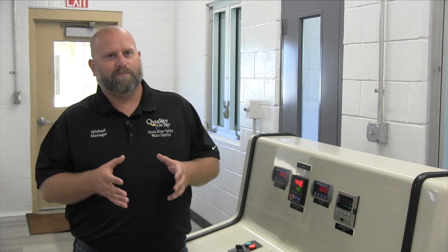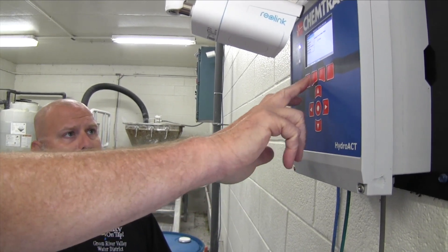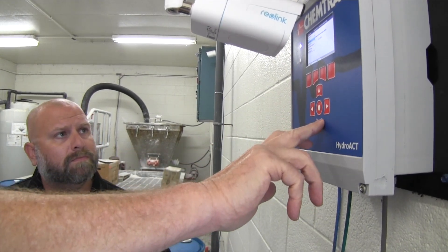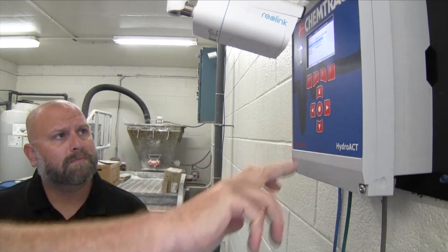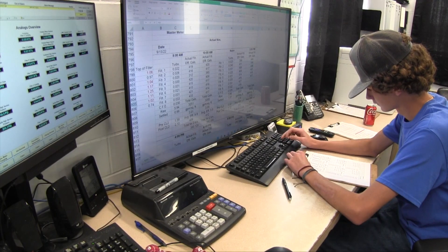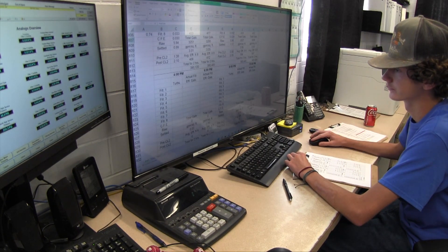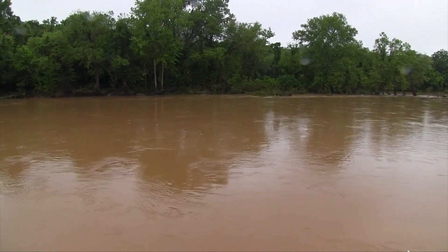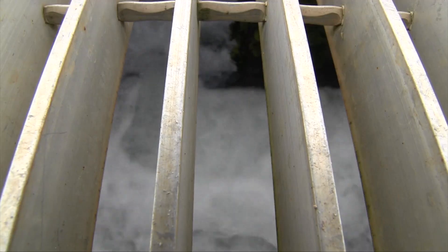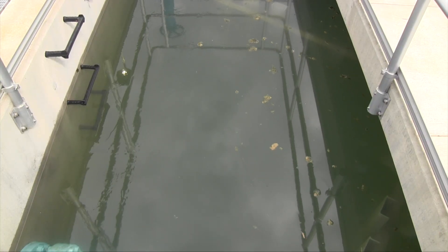It's easy to close your mind and say we're good, we did it like this back in the day, we're fine. But the greatest thing about the streaming current is I automatically know when it's time to adjust my chemical. People who are not in this industry will never understand it, but every operator in the United States understands how crucial that five minutes can be. When that mud's coming in, you don't know — but with the Chemtrac and that streaming current monitor, it literally can save you within five minutes.